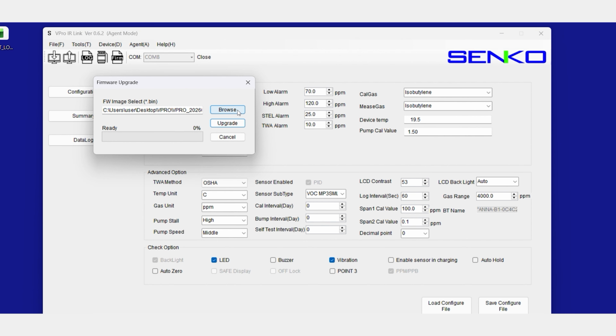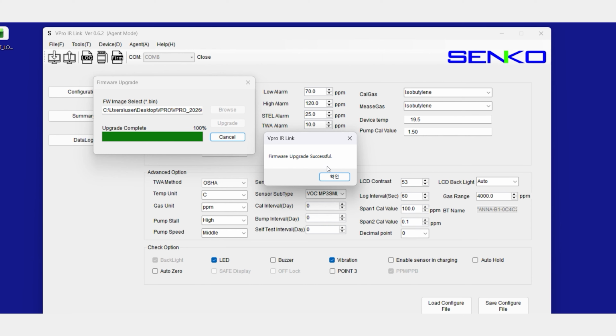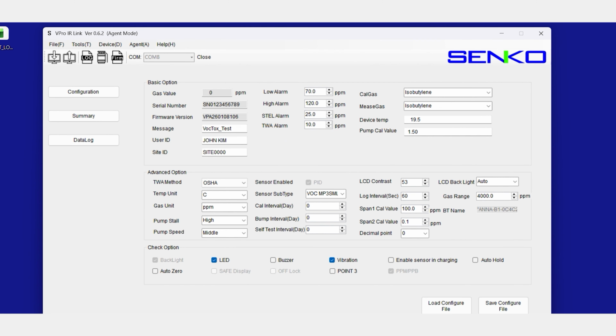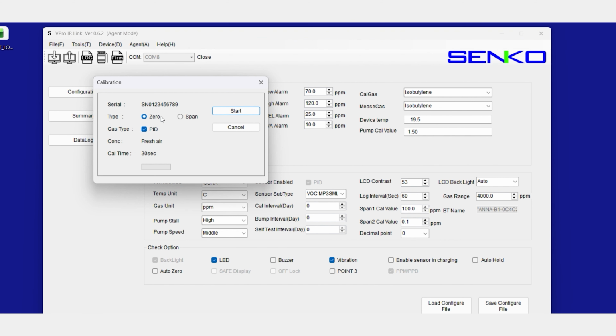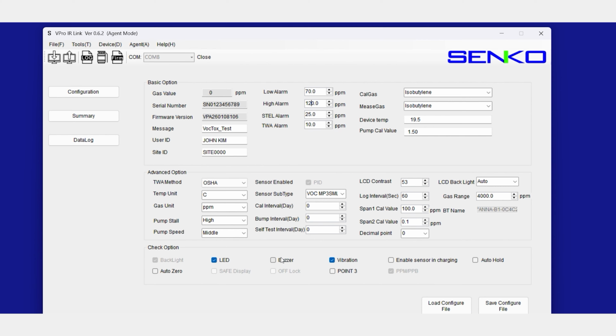Firmware upgrades are performed by selecting the provided file, and the progress status of the upgrade is displayed on the screen. Also, through IR Link, you can perform self-test execution and factory reset functions, supporting device status checks and maintenance more reliably. In addition, in advanced options, you can finally adjust overall system settings, such as pump sensitivity and speed, log storage intervals, and display settings. And in the check option, you can temporarily control the LED, buzzer, and vibration alarm to verify that alarm and indication functions are operating normally.